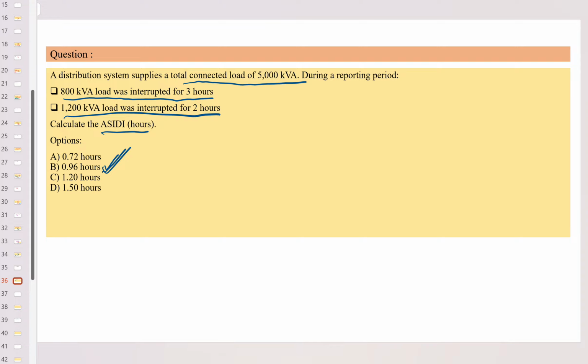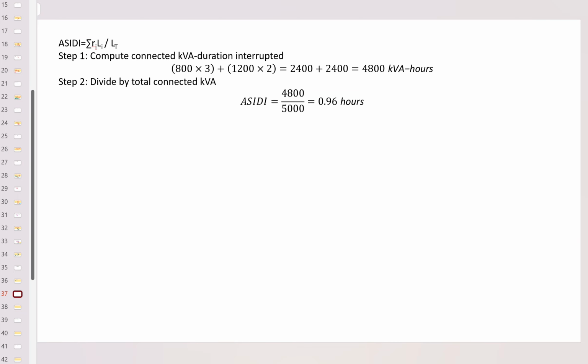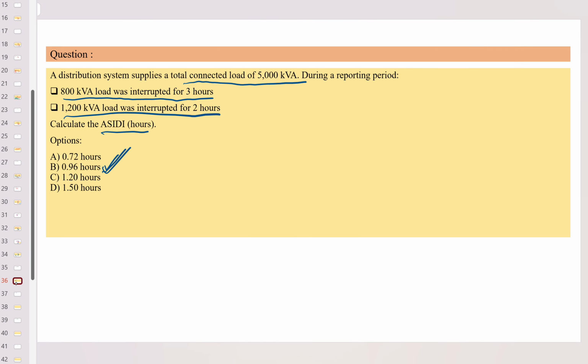Calculate the ASIDI. When you see the average time frame, it is basically the average only. So for ASIDI, you have to compute the connected kVA duration interruption. It is already written: 800 multiplied by 3 plus 1200 multiplied by 2, divided by 5,000.